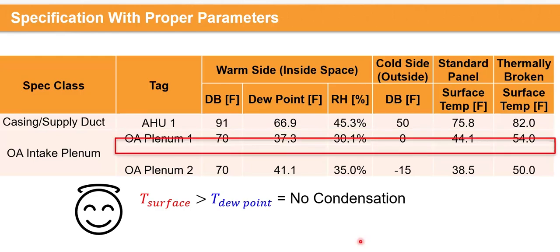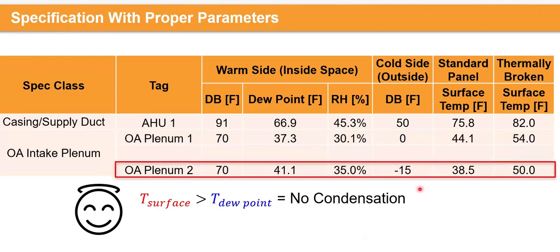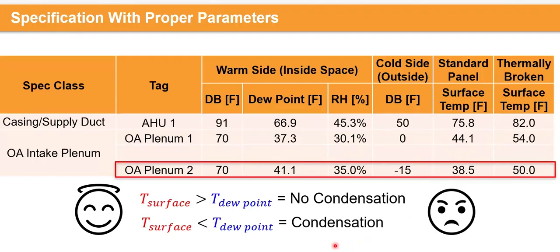But once you begin to have your much colder, frigid conditions during the winter, where you have minus 15 cold air coming in at 35 percent relative humidity, you do have a dew point of 41 degrees. Now, your standard panel would have a surface temperature that is much lower than the 41. So you would experience condensation in this regard. No one is going to be happy with that if this begins to ice up and cause issues on the site. However, the thermally broken remains around 9 degrees Fahrenheit above that dew point temperature. So this makes it much, much more superior when it comes to handling colder climates and your outside air plenums.